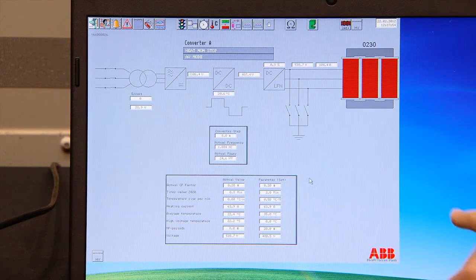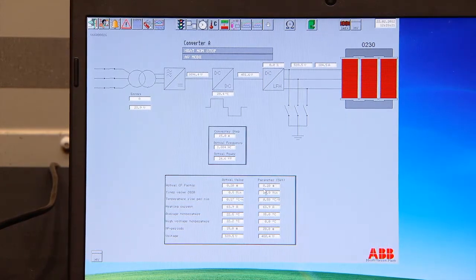We have our timer, our 2-minute timer here. We're at 0.4 minutes. After 2 minutes he will check the heating speed. We set that to 0.5 degrees per minute. We will check and see what level we have. After 2 minutes we'll probably adjust the current factor. We are running now at the minimum current factor 0.2. We will go up to maximum 0.5, and anywhere in between he will regulate.